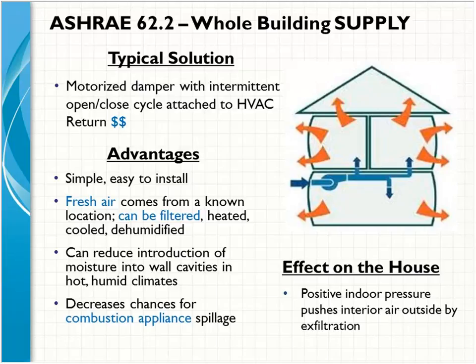Now, the advantages, of course, are that when that air is brought into the cold air return, it's going to be run across the furnace filter before it's delivered to the occupants. So that's a plus. And because it's not creating negative pressure in the building, we're not going to have the potential to impact in a negative way the combustion appliances like the water heater, for example, or a fireplace might also be susceptible to spillage if we had too much negative pressure in the building.